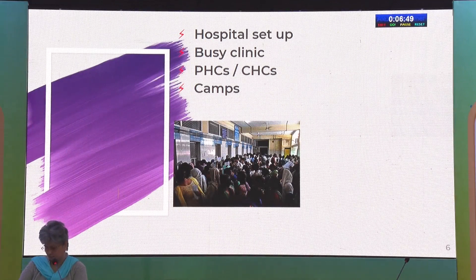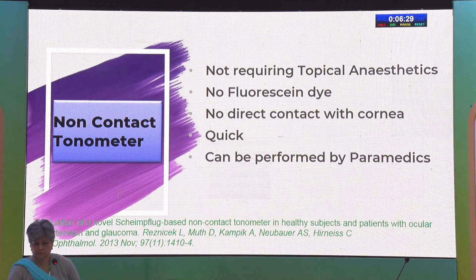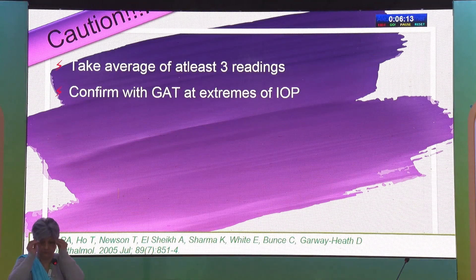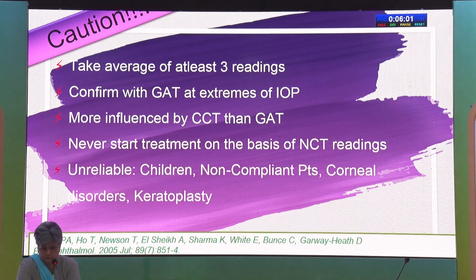In a hospital setup with a busy clinic — a PHC, CHC, or a screening camp — applanation might not be a possibility for every patient. The answer in this situation is a non-contact tonometer. This device doesn't require topical anesthesia or fluorescein dye, is very quick, and can be performed by paramedics. However, we need to take at least an average of three readings, confirm findings with Goldman at extremes of IOP, and it is more influenced by central corneal thickness than GAT. We cannot start treatment based on NCT readings alone — it is good for screening but not for treatment decisions.